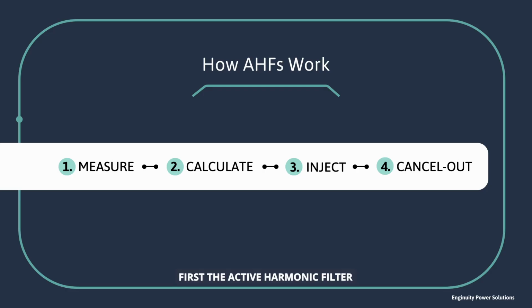First, the active harmonic filter measures current and voltage waveforms. Next, high-speed processing calculates the exact compensating signal required. Finally, the system injects that signal back into the network. The distortion and the corrective signal cancel each other out. As a result, the system restores waveform quality and reduces electrical stress across connected assets.